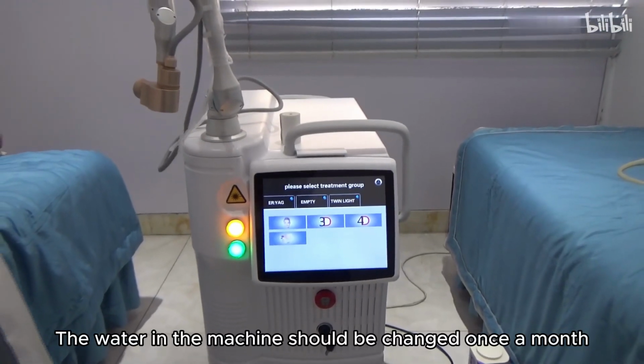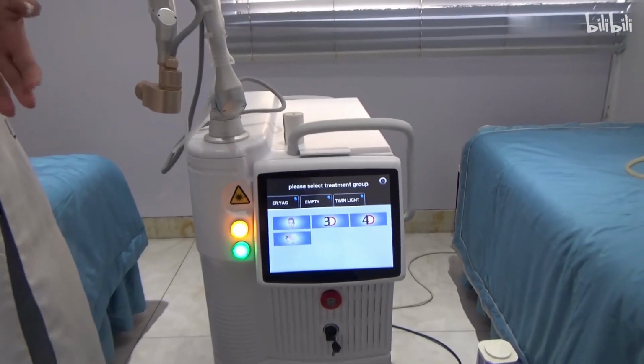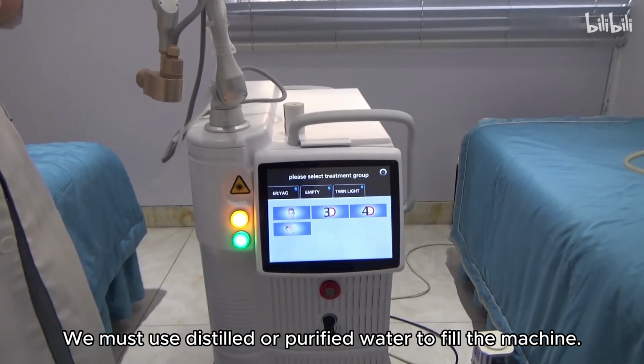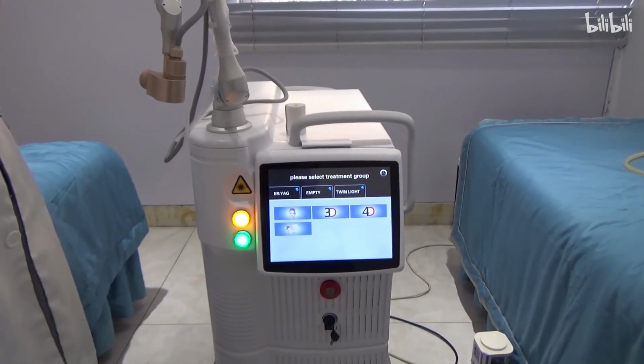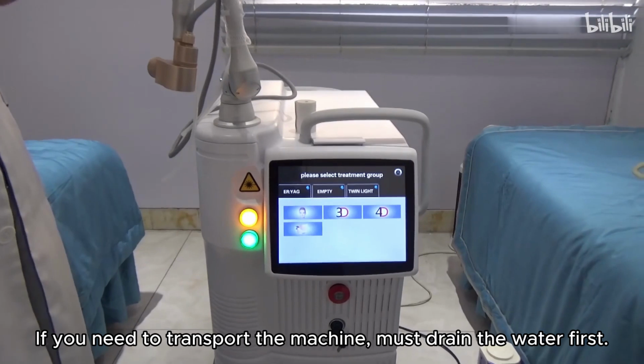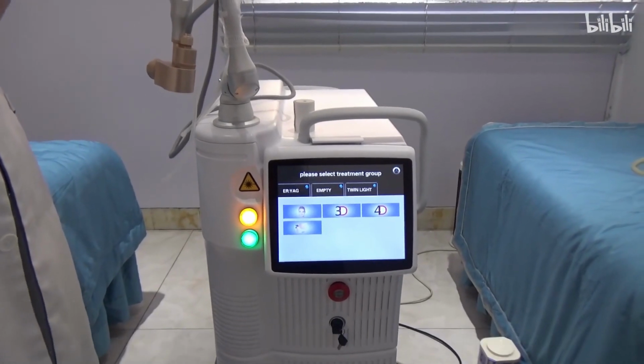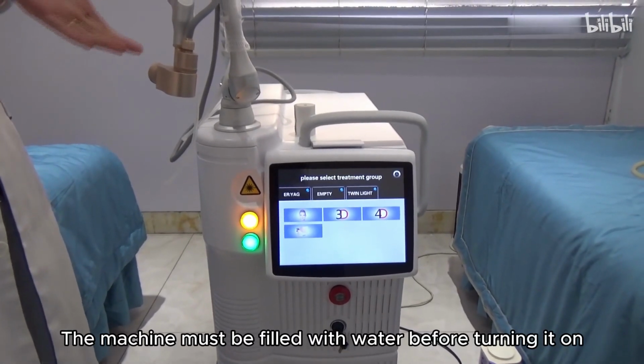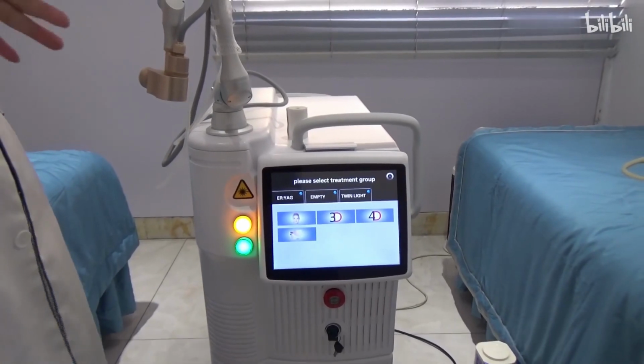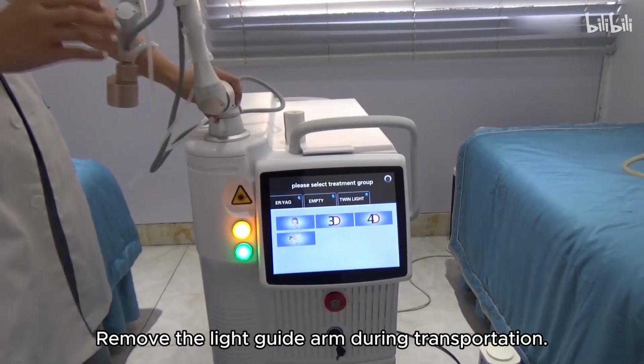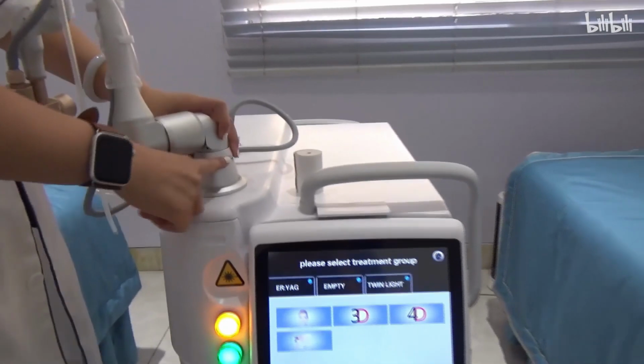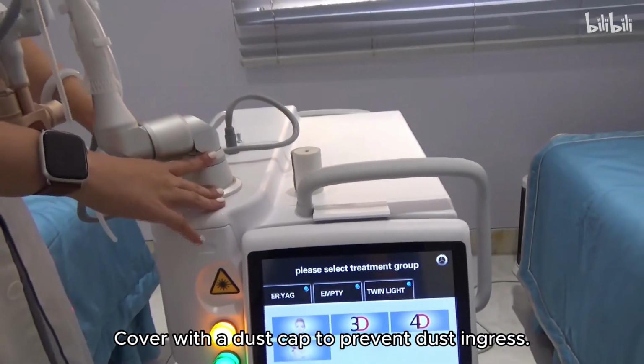The water in the machine should be changed once a month. We must use distilled or purified water to fill the machine. If you need to transport the machine, you must drain the water first. The machine must be filled with water before turning it on. Remove the light guide arm during transportation. Cover with a dust cap to prevent dust ingress.